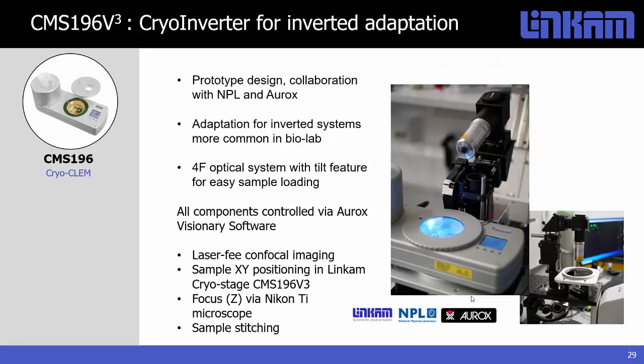This is a development still in prototype stage: a cryo inverter system that allows the cryo stage to be mounted on an inverted microscope. This has benefits because inverted platforms are most widely available in biolabs carrying out such research, and it gives very convenient access to the sample. You can tilt the whole optical system away to access the stage for sample loading, so the stage always remains mounted on the inverted system while you tilt the optics out of the way.